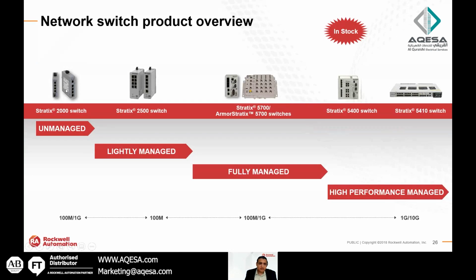If we need an unmanaged switch, we go to Stratix 2000. If we need a lightly managed switch, we go to Stratix 2500. If we need something in the middle, fully managed but with only 2 gigaports while the rest are 100 mega, plus we have 4 fiber ports or need IP67 armored, we go to the Stratix 5700.